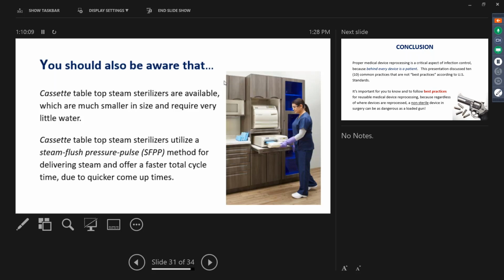If you run a complete cycle of 270 degrees for 3.5 minutes, that cycle takes about 6 minutes. If you add on their FDA cleared dry time of 60 minutes, it now takes 66 minutes. Ask your eye center if they run a 66 minute cycle using a cassette sterilizer. The answer is 100% no. I never would have bought this special cassette sterilizer unless I could get it out in 6 minutes.